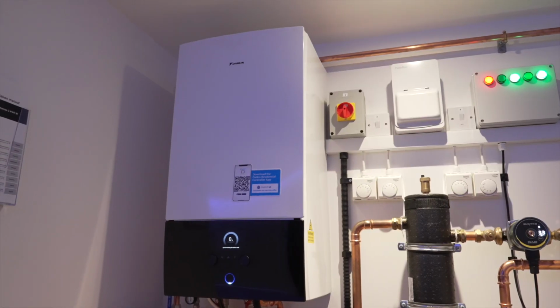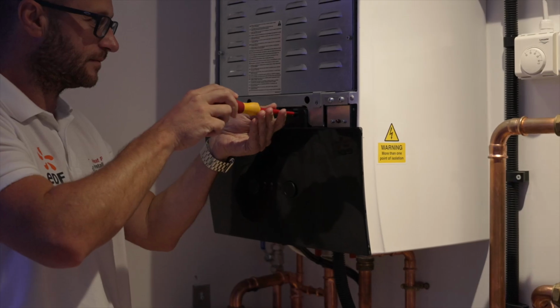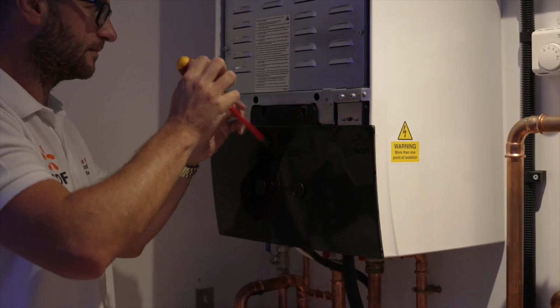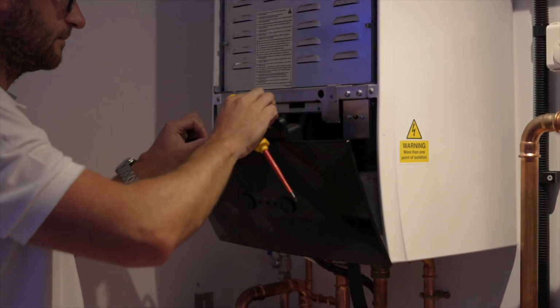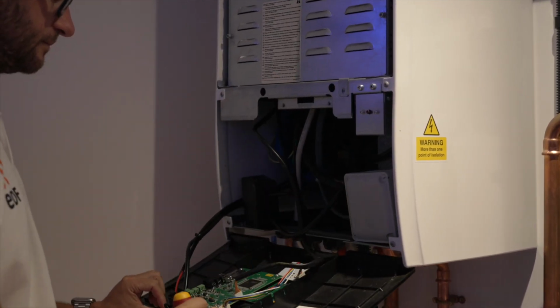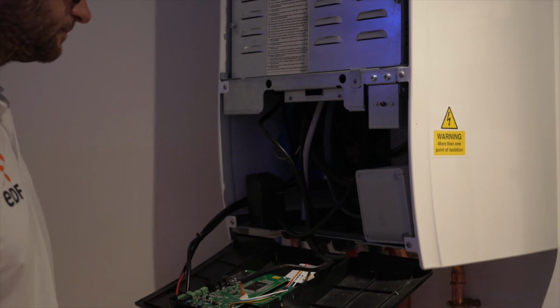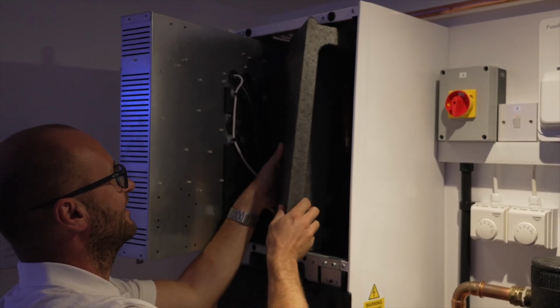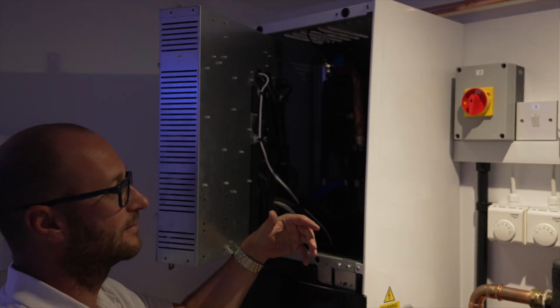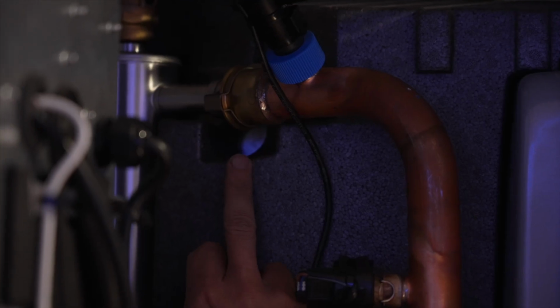The black section at the bottom has the MMI interface built into it, and there are two retaining screws that need to be undone before hinging this part down. Here you will find the slot to put the LAN adapter we found in the box earlier in the blue bag, and this then gives us access to the pump, the drain point, and the PRV pipework. Once we have access to the inside, we can remove the insulation to get to the hydraulic components. First thing we need to do is find the hole in the back to put the screw in for the hole that we drilled and plugged in the wall when we hung that bracket.